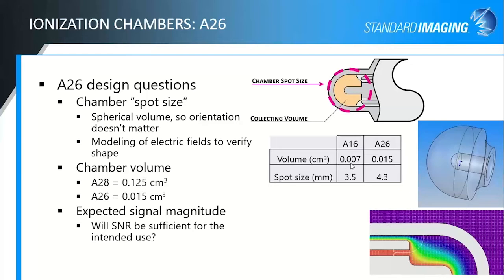The A16 is our smallest chamber. This one's been on the market for quite a few years now, and it's the 0.007 chamber. Its spot size is 3.5 millimeters. That's the sphere, this circle that encompasses all of the active region. The A26 is less than a millimeter larger, and you get twice the volume. Here, actually, is a bit of an advantage, because of the way it was designed, you don't have those polarity effects like you do with the A16, but you've doubled the signal that you're getting with less than a millimeter increase in spot size.